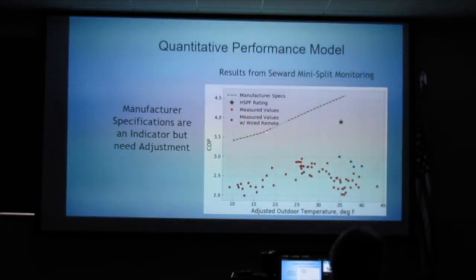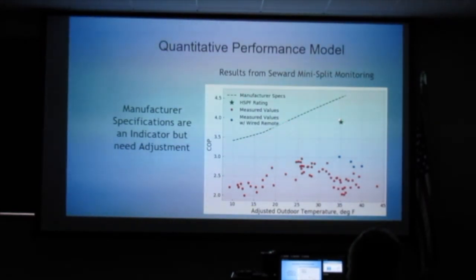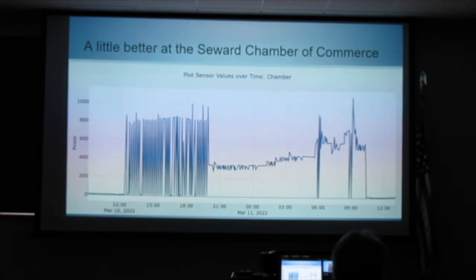Here's what the manufacturer says the COP should have been on this unit, and here's what I was actually getting: 2.5, then back down. They were claiming at 10 degrees it should have been up at 3.5, 350% efficiency, and just climbing. That HSPF number said we should have been around here. So it was kind of disappointing.